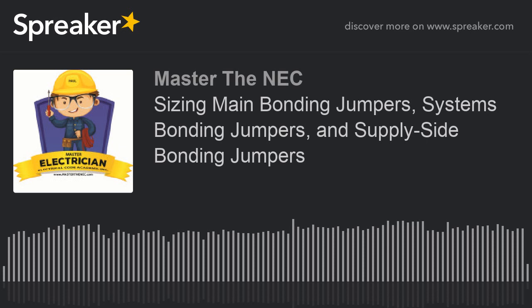So here's our case. We have a 500 kcmil. We go down the left side, and we see that over 350 through 600, if it's a copper bonding jumper, then what we've got here, a supply side bonding jumper, then we've got copper, and it would be a 1/0. So that would be the 1/0 is what we would run to that bonding bushing with a bonding jumper. And we're done. And it connects over to the enclosure. Okay? Done. Happy. That's a bonding. We bonded it. All right?